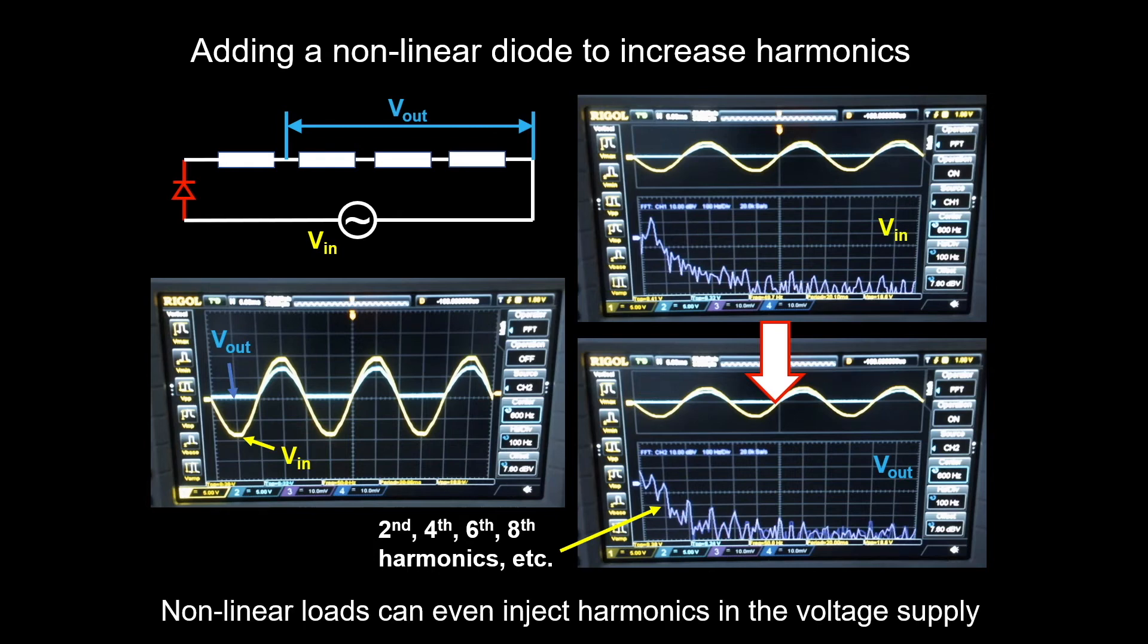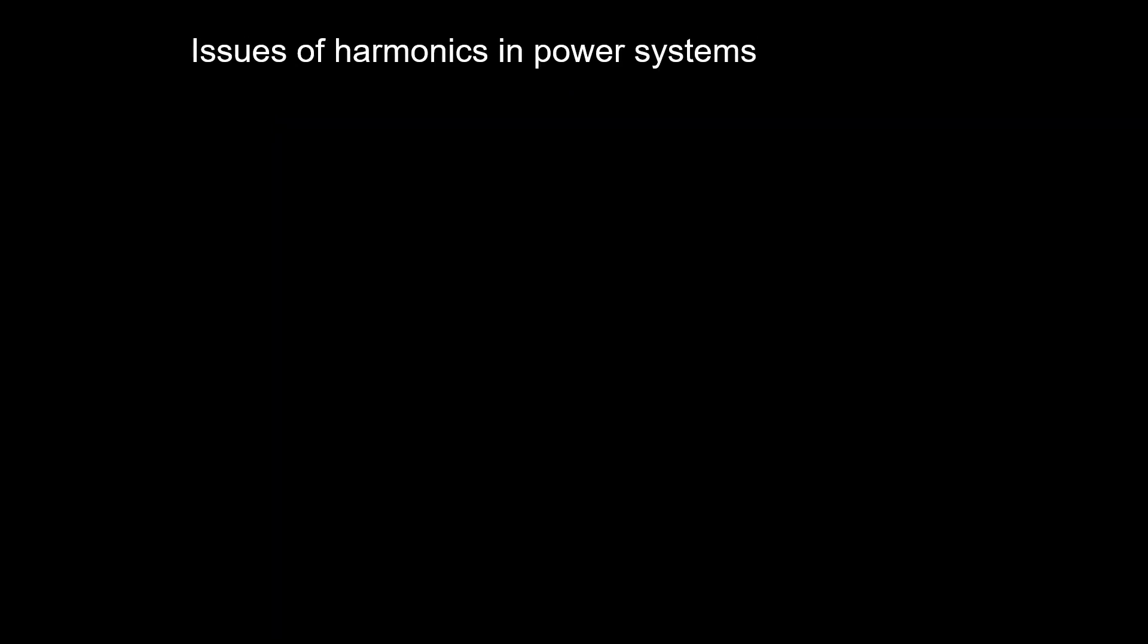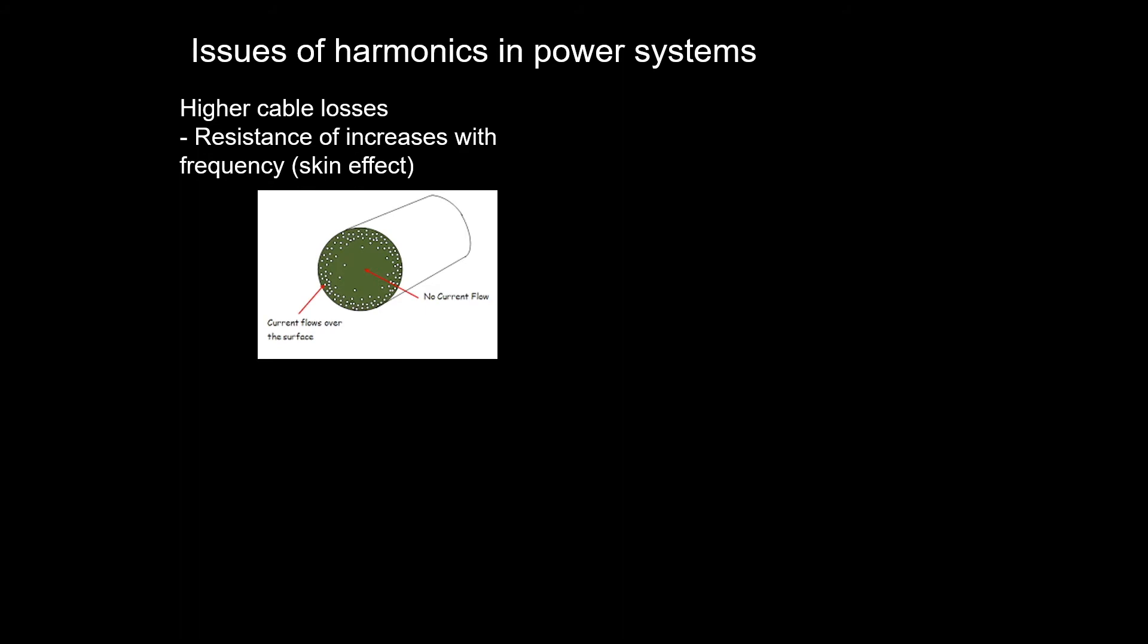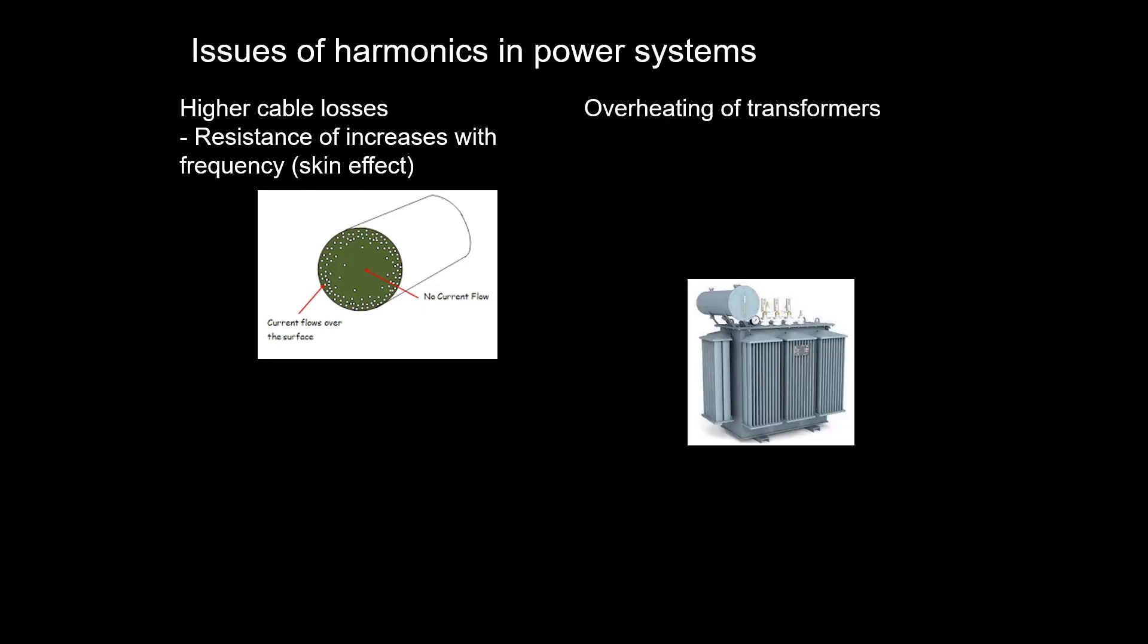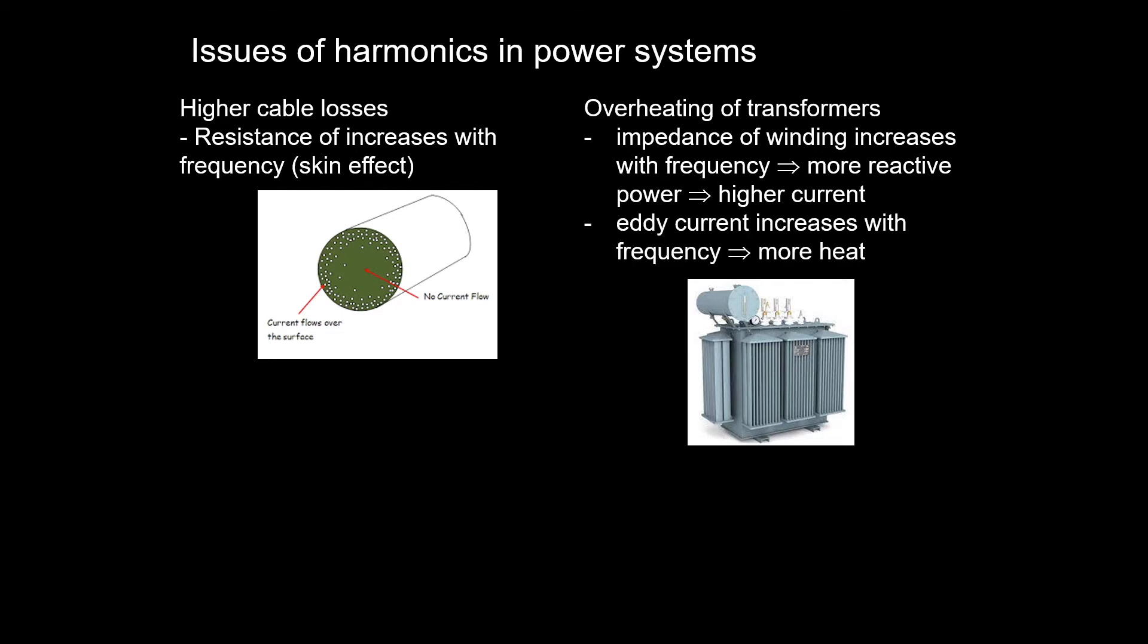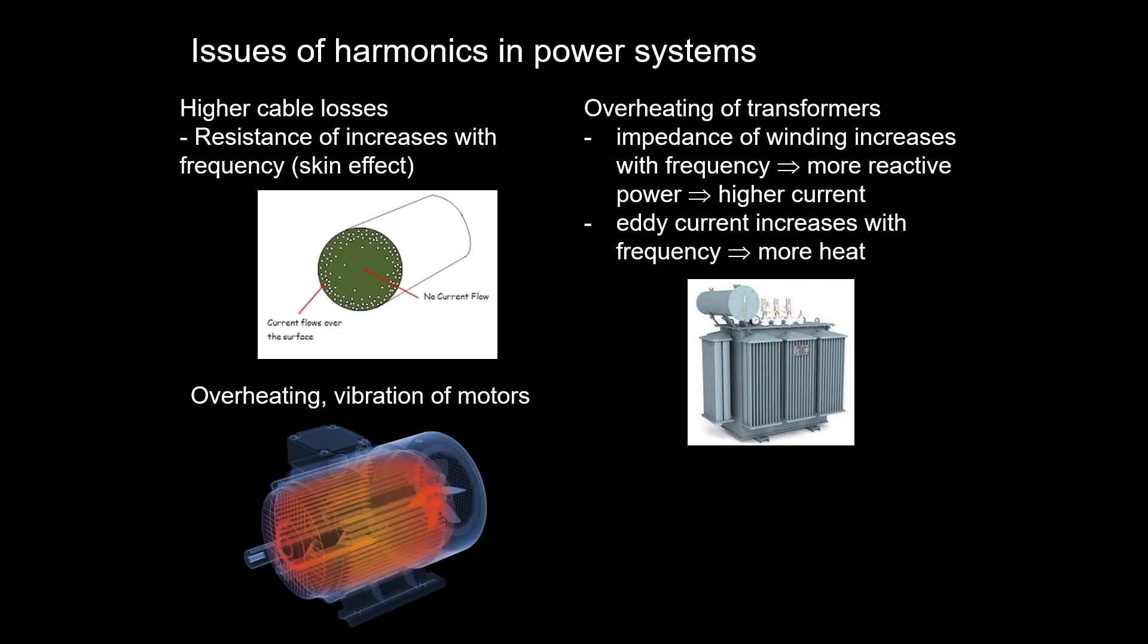Sometimes the non-linear load can even cause harmonics in the power supply. So you may wonder, what are the problems of harmonics in power systems? First, it will create higher cable loss as the resistance increases with frequency, known as skin effect. Second, it will cause overheating of transformers. The impedance of the winding increases, so there are more reactive power and higher current in the transformer. At the same time, eddy current also increases with frequencies. Third, harmonics can cause overheating and vibration of motors.